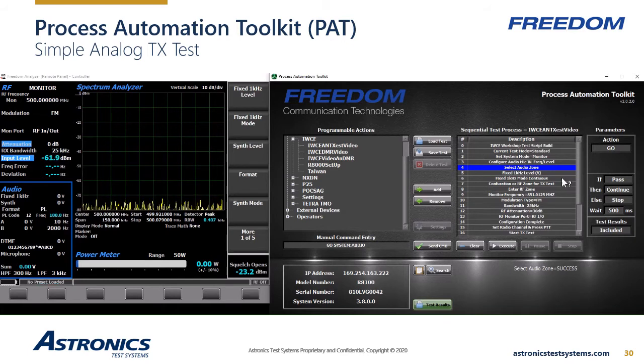Now remember the prerequisites. You have to be in a zone to use the commands from within that zone. So I had to go to the audio zone to be able to set up this audio oscillator. So I'm going to set the fixed 1 kHz level to 200 millivolts, send command, and then need to turn the audio oscillator on, set to continuous. R8100 confirms that the audio oscillator is on in a continuous mode. That completes the audio setup.